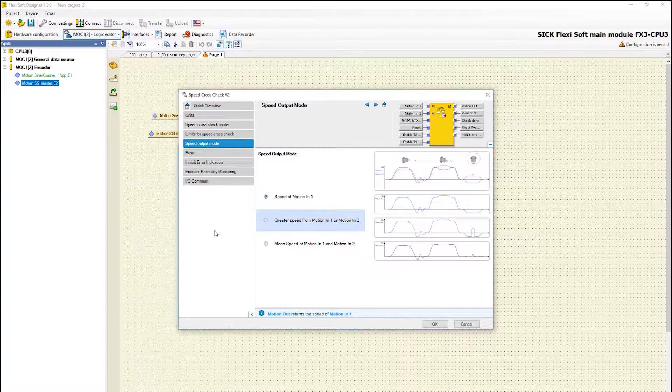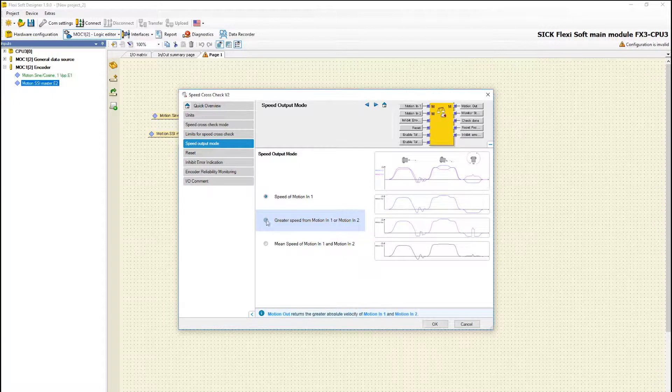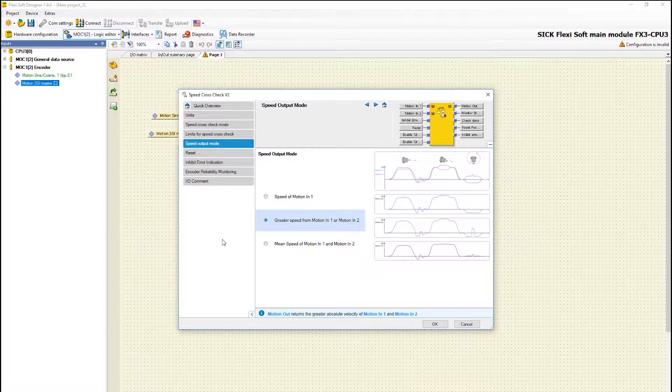The option greater speed of motion 1 or motion 2 should be selected if the higher value from two encoders is to be used for further evaluation. For example the speed of the outer wheel of an AGV is of relevance during cornering.